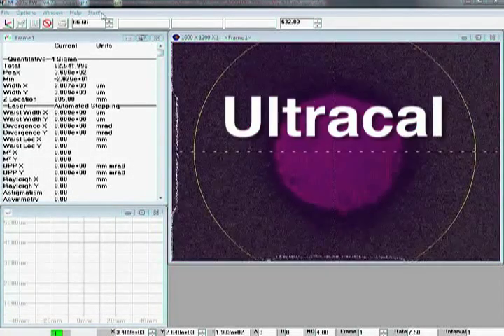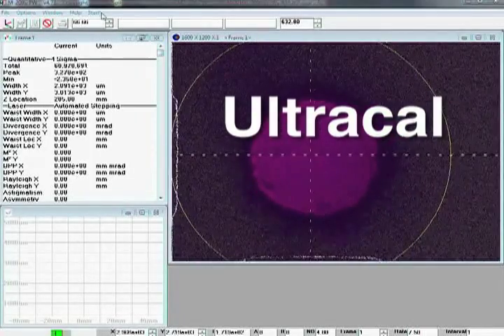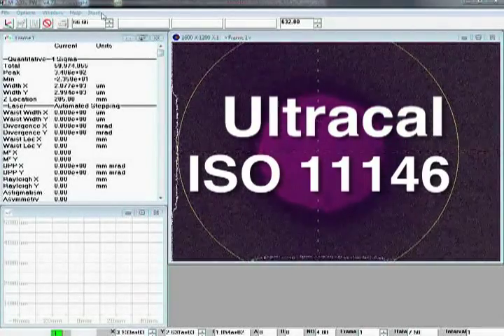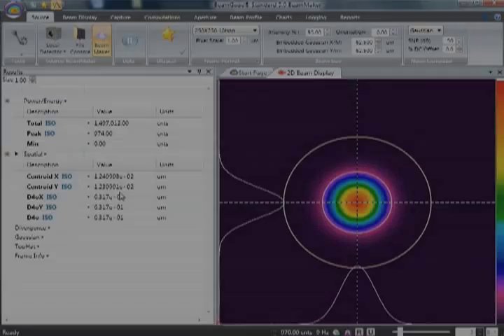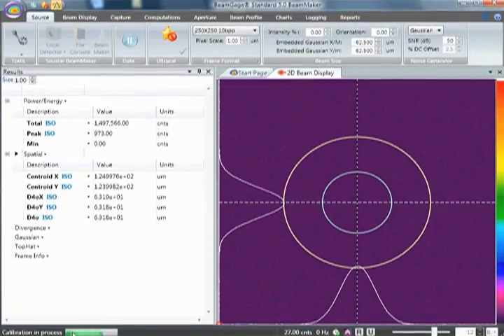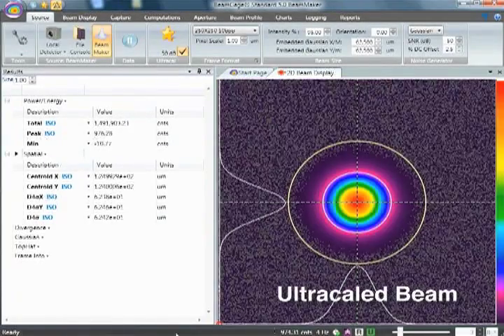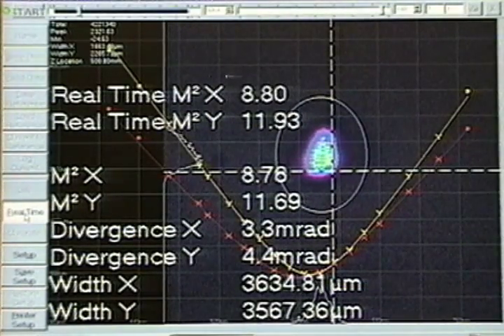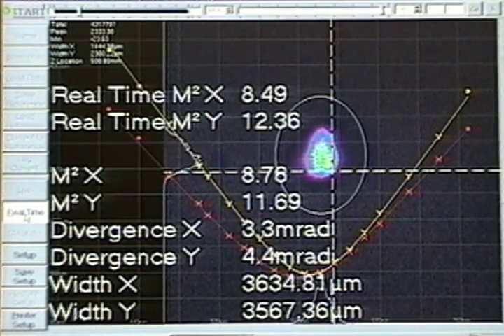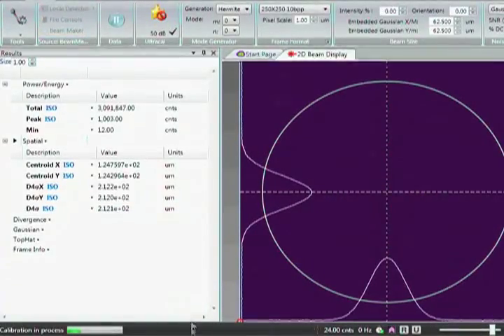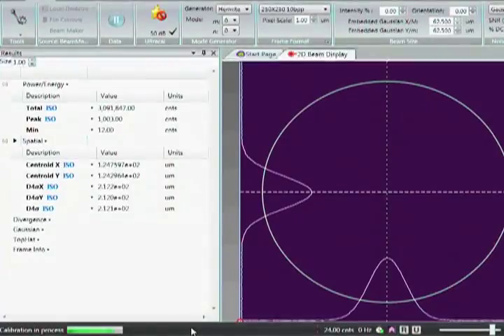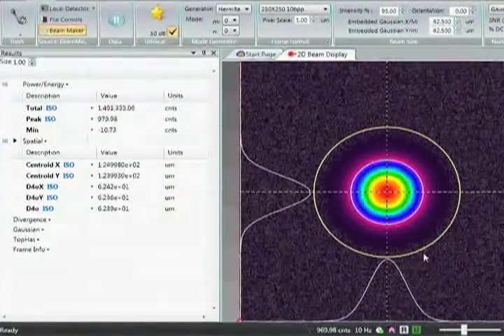When necessary, the system performs the patented UltraCal, which resets the baseline in accordance with the ISO 11146-3 specification. UltraCal assures the measurements of the beam widths are as accurate as possible. Spiricon developed its UltraCal algorithm in the early 1990s. ISO later recognized this methodology to ensure beam measurement accuracy in ISO 11146-3, finalized in 2005.